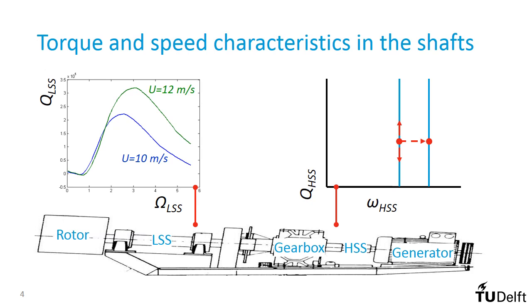This testing machine can be set at any rotational speed. If the wind speed is blowing at 10 m/s and the testing machine would gradually increase the rotational speed in the low-speed shaft, the torque measured by the testing machine would follow the blue curve from left to right. Now for the high-speed shaft: disconnect it from the gearbox and connect it to the testing machine. Let the testing machine apply a torque on the high-speed shaft and measure the rotational speed. It will be clear that the machine will measure the speed as it is set by the electrical frequency.